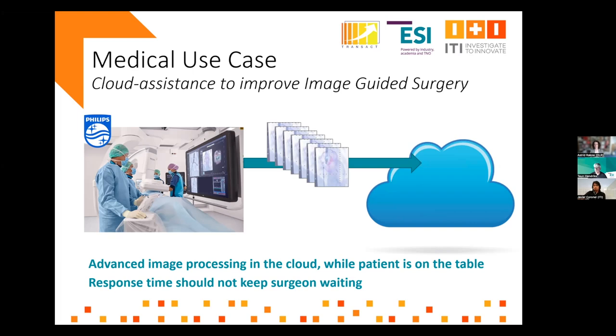These systems were previously connected to the cloud only for patient information after the operation. What is happening now in this project is we're looking at how to connect these systems to the cloud during the operation itself. There can be reasons like a difficult procedure where, rather than only having a 2D view, you may want a 3D scan to better examine whether the procedure is going right. This may happen a number of times during an operation of 30–40 minutes. The surgeon issues such a request, the arch makes a rotation around the patient, collects between 200 and 600 images, which are then collated and reconstructed into a 3D model for the surgeon to examine during the operation.